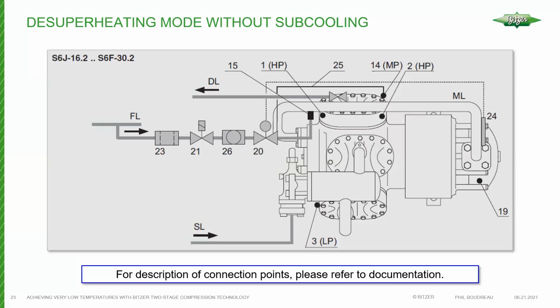This is another mode that you can operate the compressor with. And this is, again, as I mentioned before, basically the minimum that we can apply. The desuperheating only mode is the minimum. This gives you basic desuperheating of the interstage so that we don't overheat the compressor and burn up our oil, and to ensure we have enough cooling for the motor and what have you. It's the minimum. But of course, when we apply it this way, we can't take advantage of subcooling. But there may be other reasons to apply this.